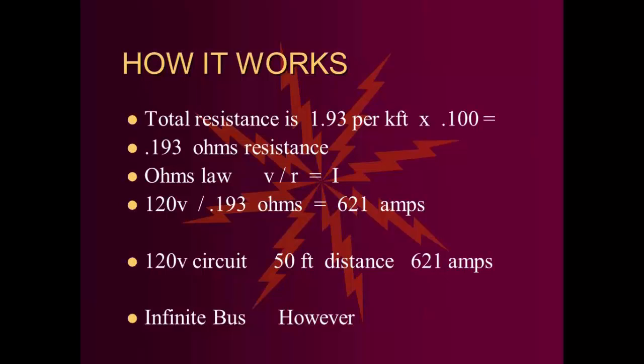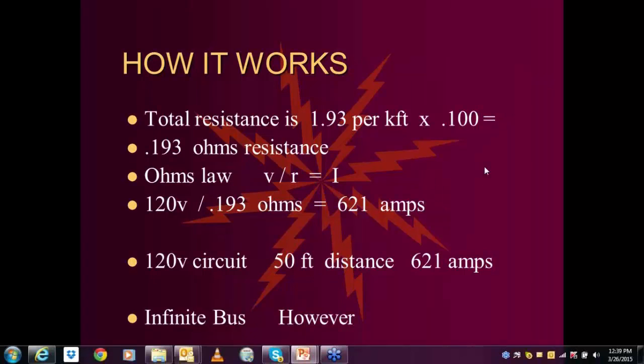Now we have our voltage and we have our resistance. How many amps of current flows on that 50-foot run? Ohm's law, voltage divided by resistance equals current. 120 volts divided by 0.193 ohms of resistance gives you 621 amps. Now you think about that for just a minute. That's a 120 volt circuit. The distance is 50 feet.